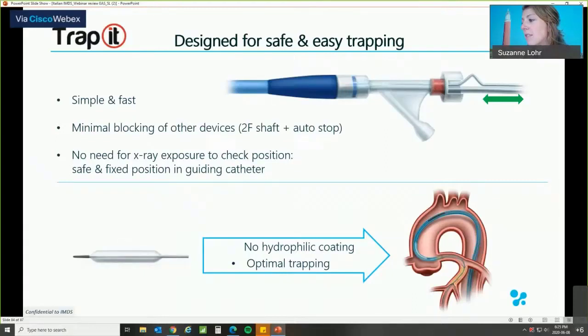The Trapit is simple and fast, since you don't need any visualization for the position of the tip. The tip of the Trapit is visible on the angio, but there is no need to check the position. So there's no need for X-ray exposure, which is very fast. The device can be inserted, the balloon can be inflated, and you can do your trapping. The device can be deflated, and it will retain its very flat shape. Together with a very small 2 French shaft and the same size of the auto-stop, there's minimal blocking of other devices. So especially, for example, when using a 7 French, a Trapit can just be left inside the guiding catheter during a procedure because there's no blocking of other devices. Other devices can just be inserted and removed from the guiding catheter and the hemostasis valve.